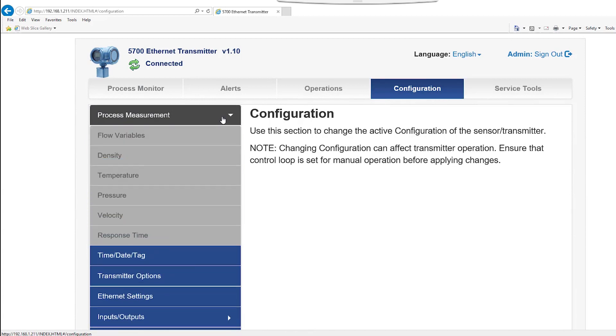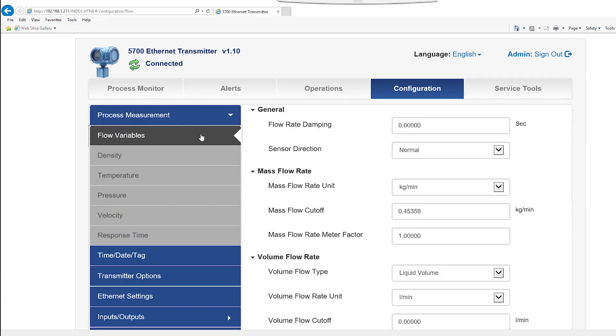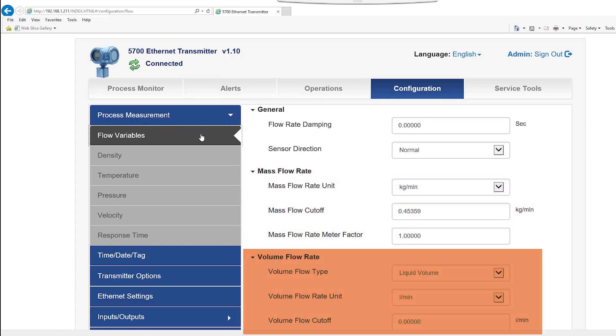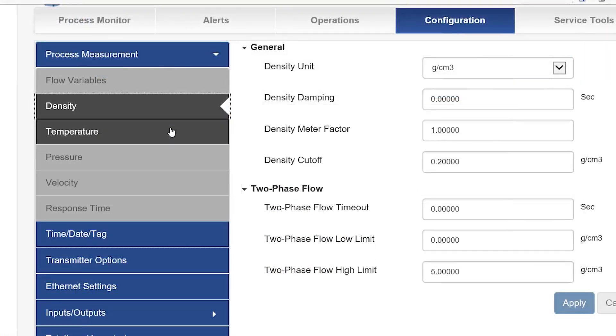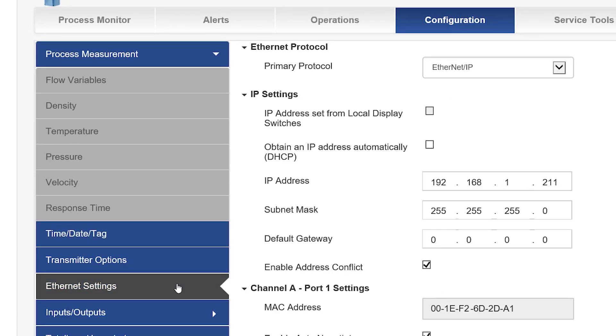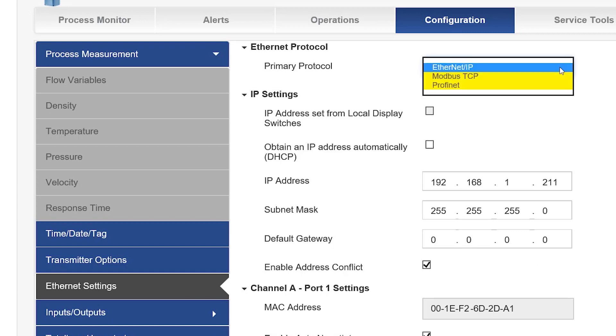Selecting the configuration tab allows the user to configure flow variables such as mass flow and volume flow. Temperature and density units can also be configured. Time, date, and tag allows the user to configure the integrated real-time clock setting and tag information. Ethernet settings allows the user to configure the Ethernet protocol, which can be changed from Ethernet IP to Modbus TCP or Profinet.